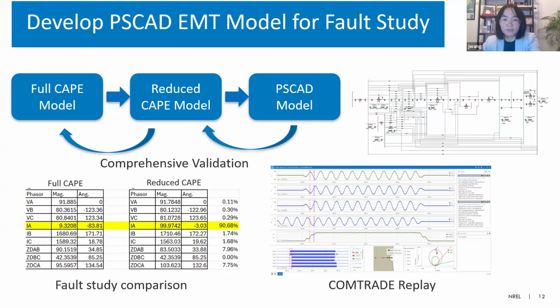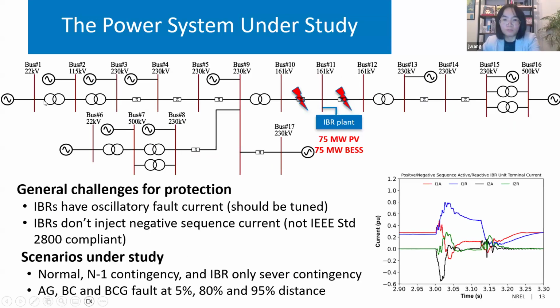And then the next slide shows you the power system under study. So this is the model we use to do the fault study. Bus 10 and bus 12 are the transmission lines connecting many solar plants. For this study, we did only one IBR plant that has a 75 megawatt PV and a 75 megawatt BESS, because that's the operational condition now. The other plants are under commissioning.